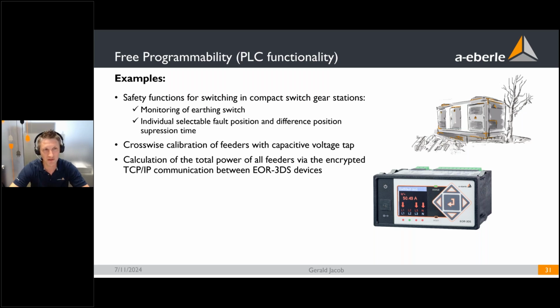Other examples would be crosswise calibration. If you do not have a very precise voltage measurement in every single feeder, you could also share information from one field with other devices in other fields. Another example would be the calculation of the total power. If you have, for example, 4 devices installed in all cable fields and you want to calculate locally, some kind of edge intelligence, the total power of the secondary substation, this would also be possible.